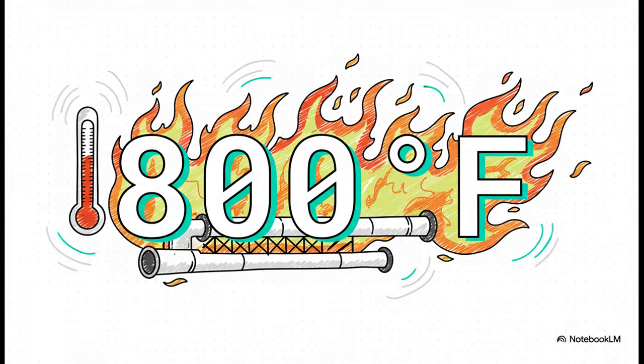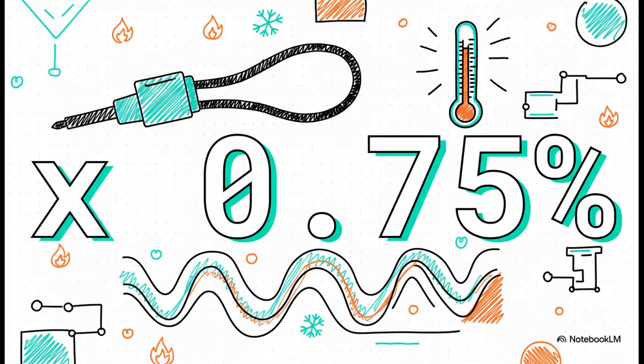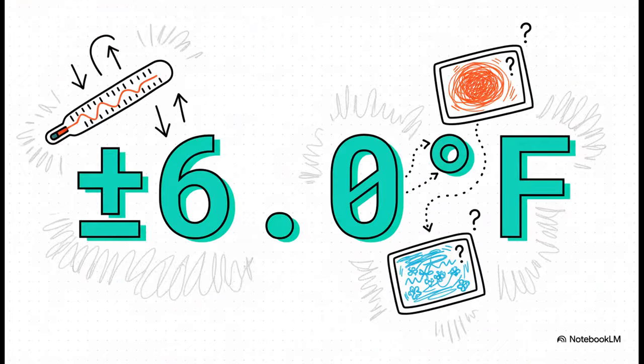All right, so the temperature we need to measure is 800 degrees Fahrenheit. Simple enough. Now, the official industry standards say that a standard type K sensor in this heat has a built-in tolerance, or error, of plus or minus 0.75%. You run that simple math, and what do you get? A potential error of plus or minus 6 degrees Fahrenheit. Now think about that for a second. That means your screen could say 800 degrees, but the real temperature could be as low as 794 or as high as 806. That's a massive 12-degree window of uncertainty.